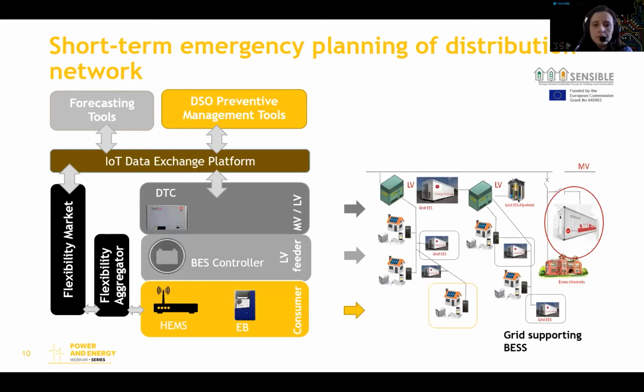So the tool was tested in a real demonstration pilot, as I said, in the context of the European project SENSIBLE. And you can see on your right side the real medium voltage pilot system that consists of a medium voltage consumer and two public low voltage distribution networks. And we have here two main storage devices with grid forming capabilities, so they are able to ensure an islanding operation of these low voltage networks.